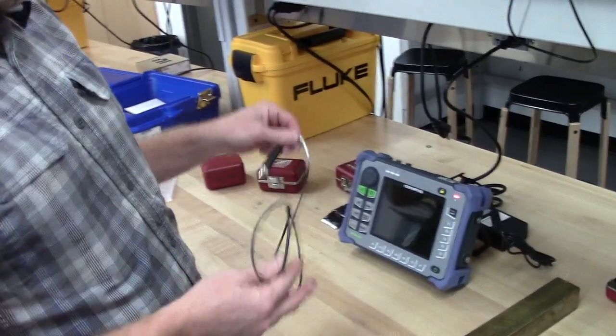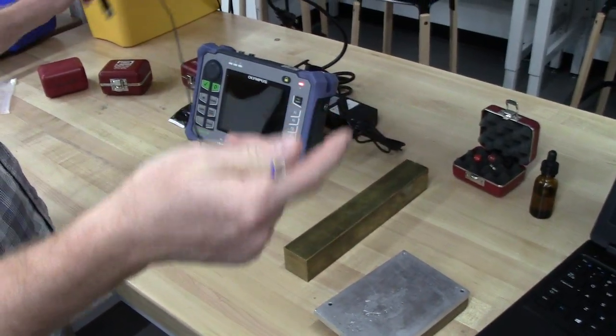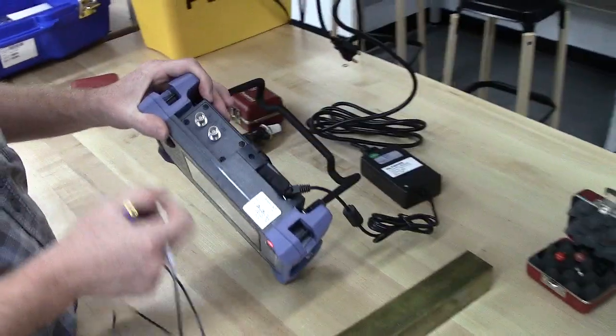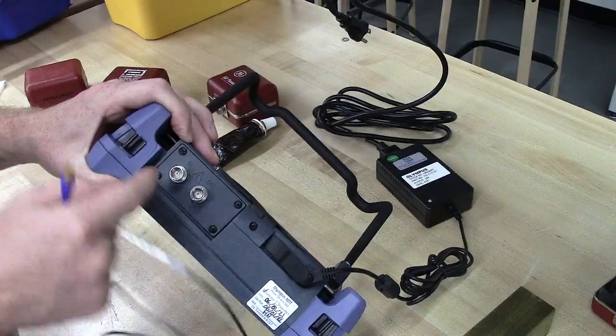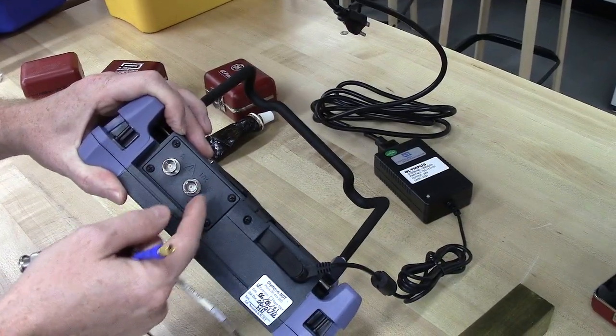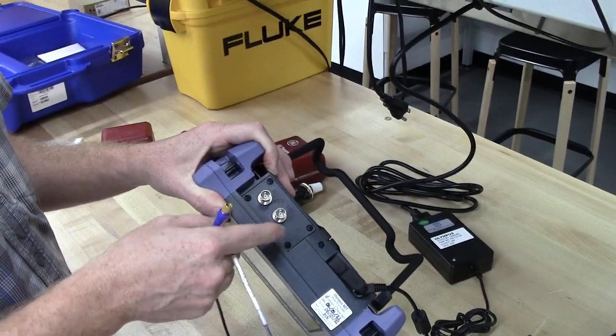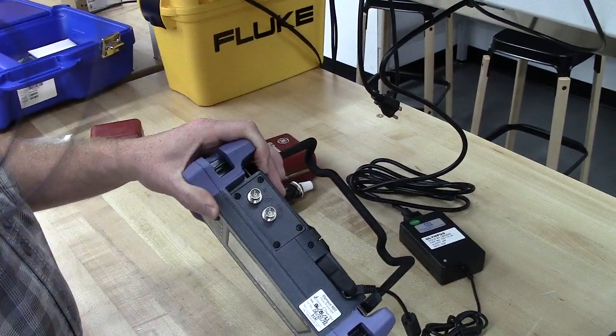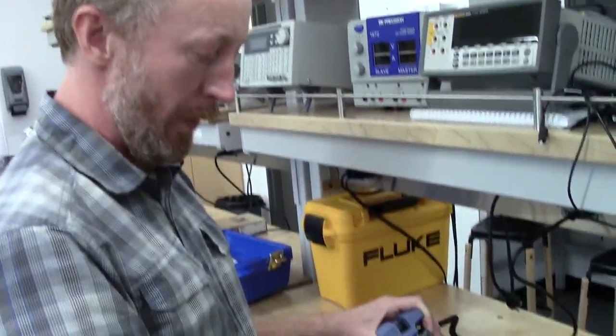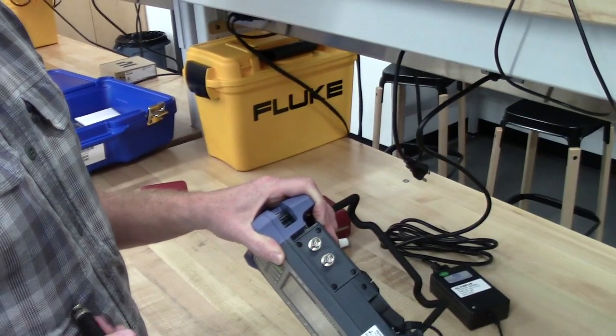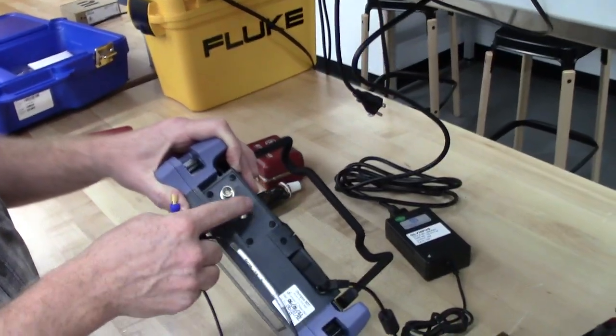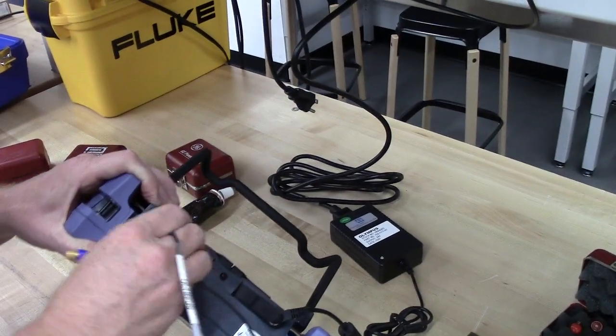And the other hardware connection you need to make is to connect the transducer. And we use a mini-coax cable for that. And there are two options for this on the top here. There's one coax connection with an R and then another with a T slash R. And you can set this up in lots of different configurations. One would be to use a transducer to transmit the signal and then another one to receive it. And in that case, you would use both. But what we're going to do is just use one to both send and receive the signal. So we'll use the T slash R input.